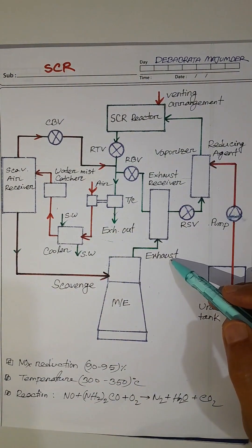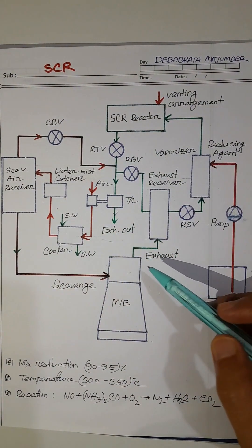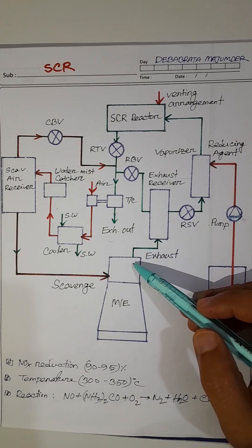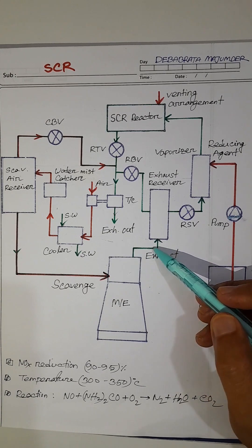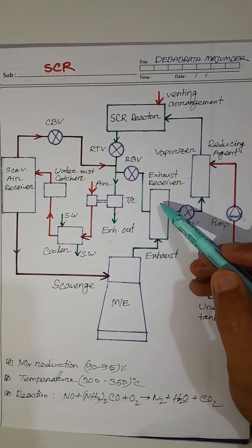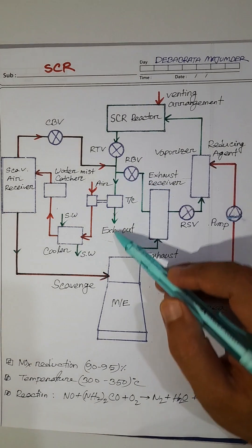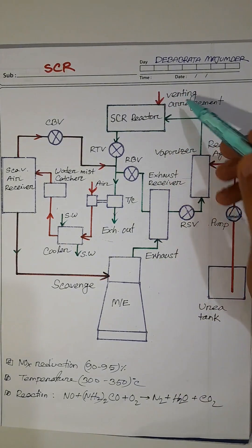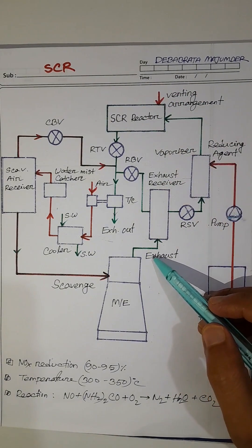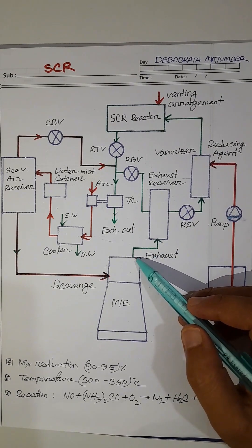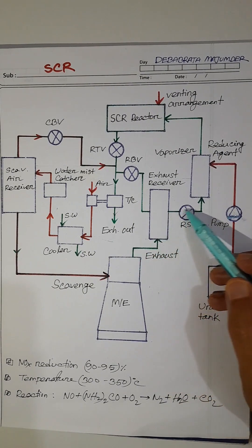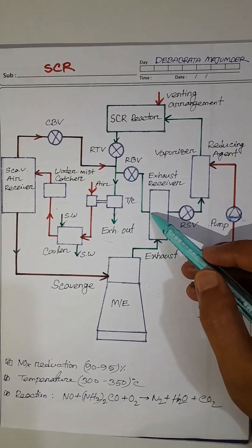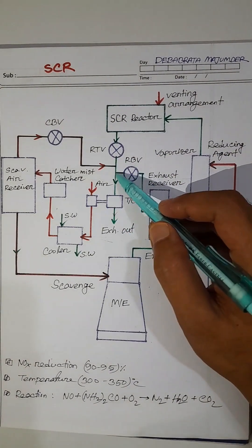In short: when the vessel is running in Tier 2 area, exhaust flow goes here and out, and at that time venting arrangement is done. When the vessel is running in Tier 3 area, the flow goes through the vaporizer, through the reactor, and out through the turbocharger. Some exhaust gas will also be bypassed.